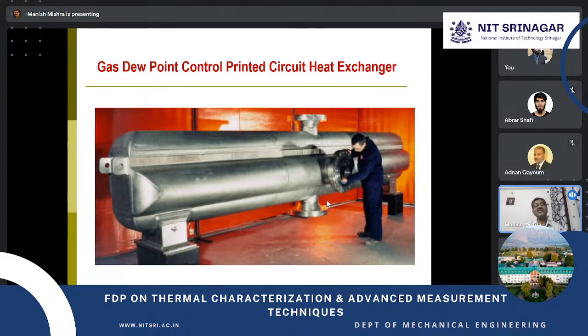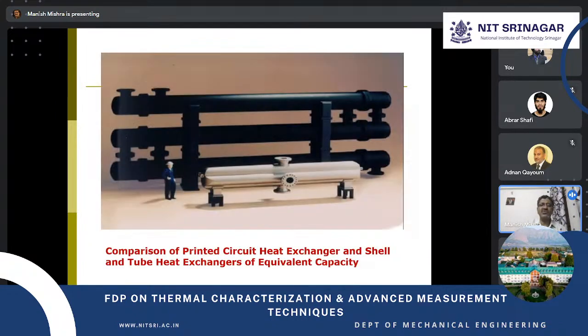It is as good as a shell and tube heat exchanger in dimension, bigger things. But if you see the capacity, the heat transfer area, surface area density, or heat capacity it may handle, just compare: this is the shell and tube heat exchanger, and correspondingly for the same application, if I design the PCB heat exchanger, it will be a much smaller version. This much reduction in dimension or size is there, and that's why nuclear reactors use these kinds of things.